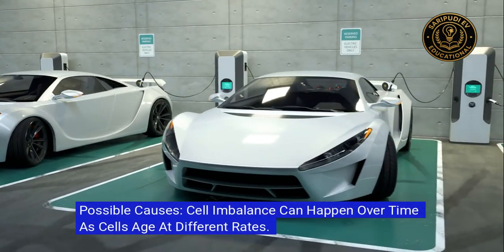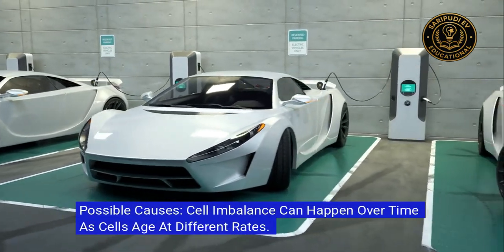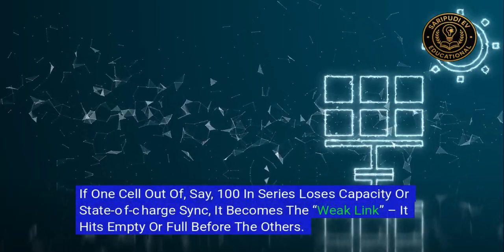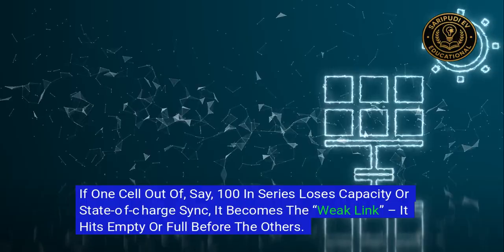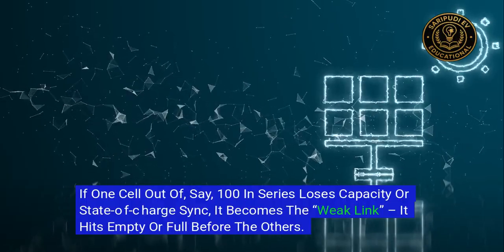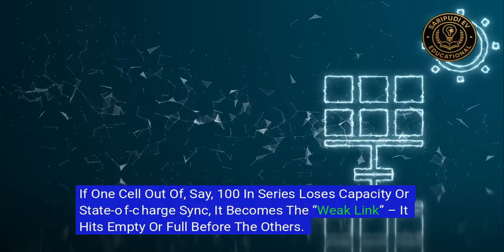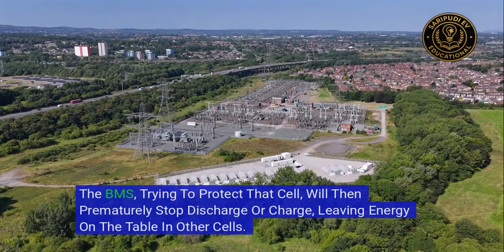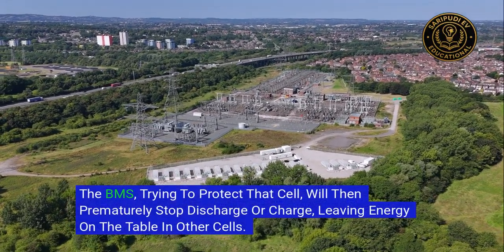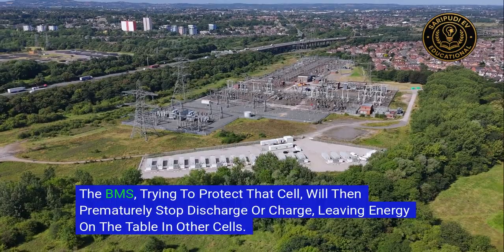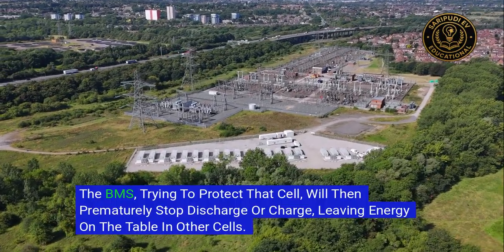Possible causes. Cell imbalance can happen over time as cells age at different rates. If one cell out of, say, 100 in series loses capacity or state of charge sync, it becomes the weak link, it hits empty or full before the others. The BMS, trying to protect that cell, will then prematurely stop discharge or charge, leaving energy on the table in other cells.